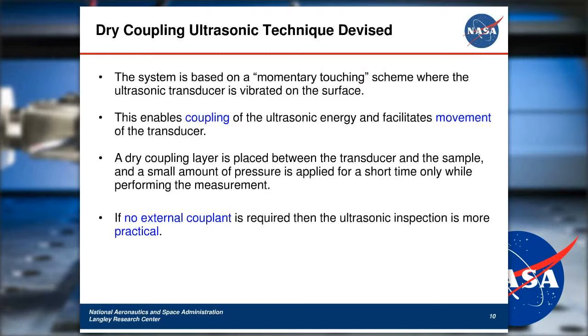Okay, the other thing this momentary touching scheme does is it allows you to move the transducer across the surface. So that's the two benefits of that. It's a very simple idea. Now the transducer has a small dry coupling layer between the transducer and the structure that you're inspecting.